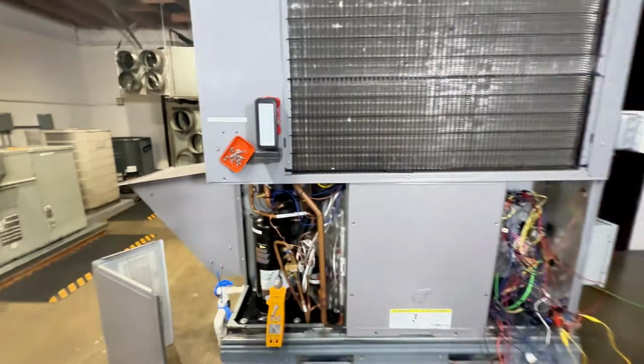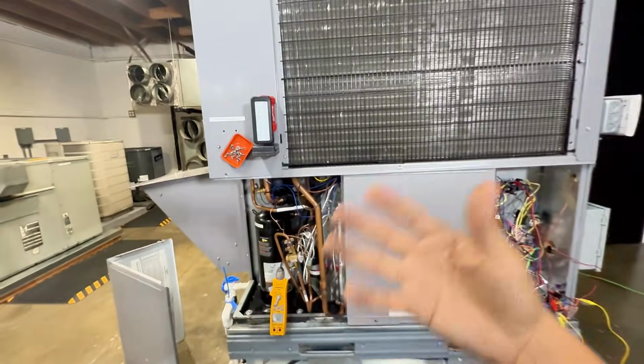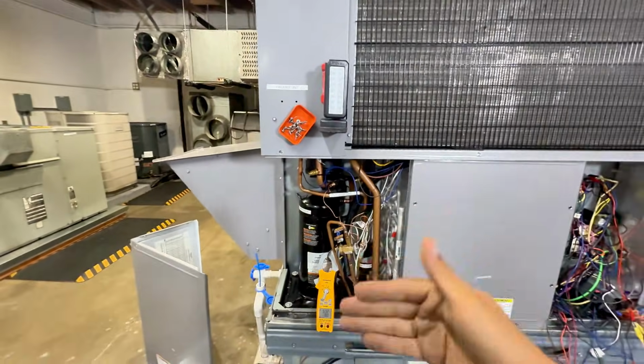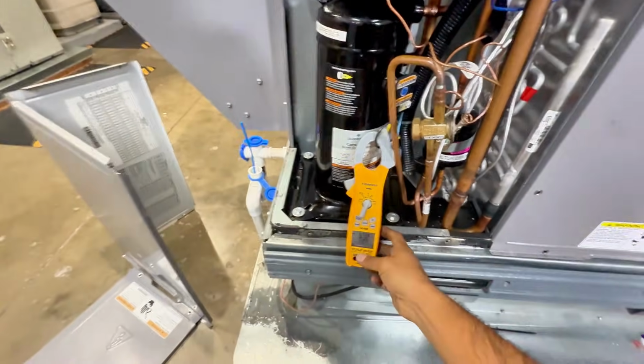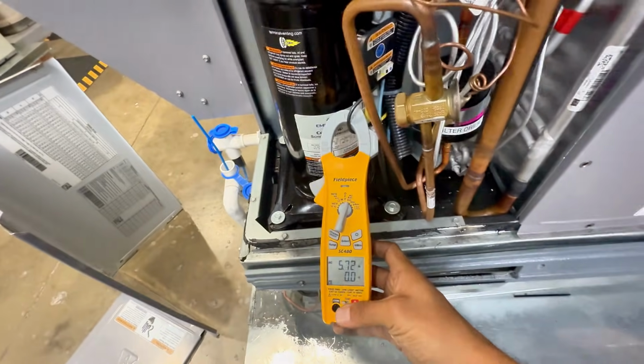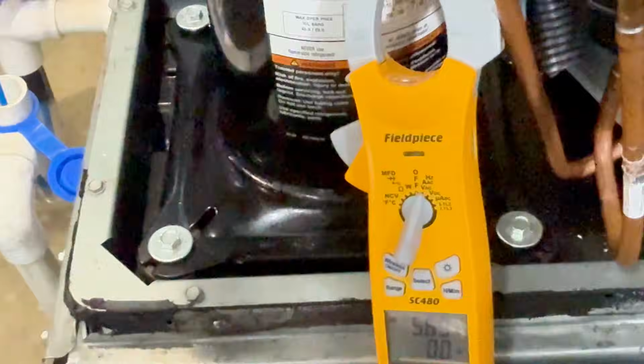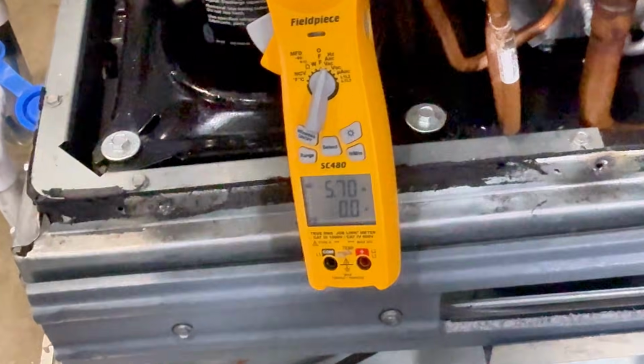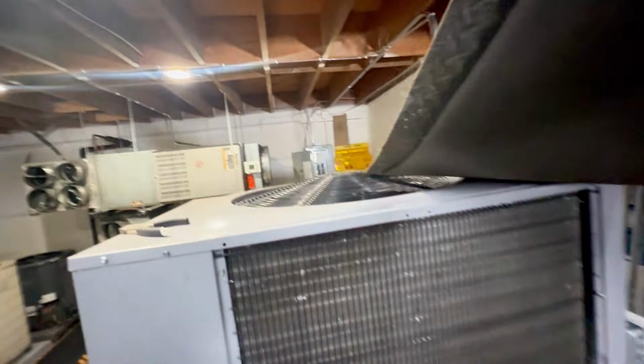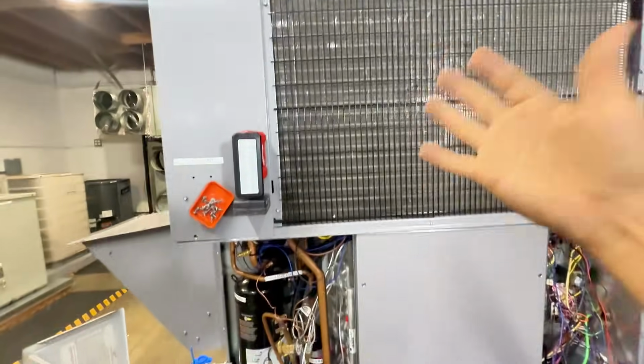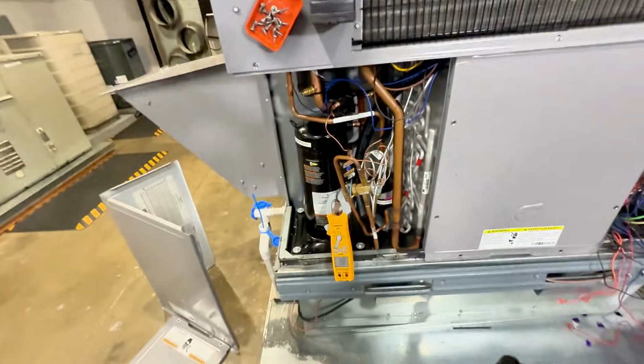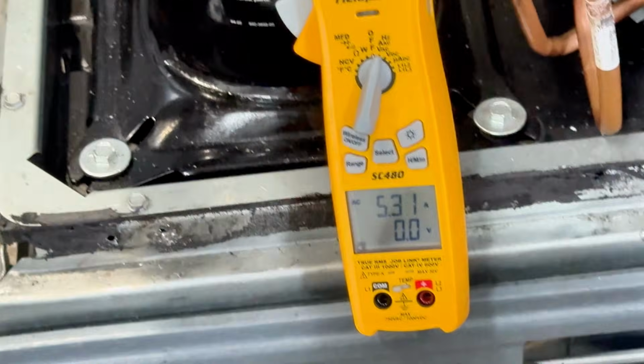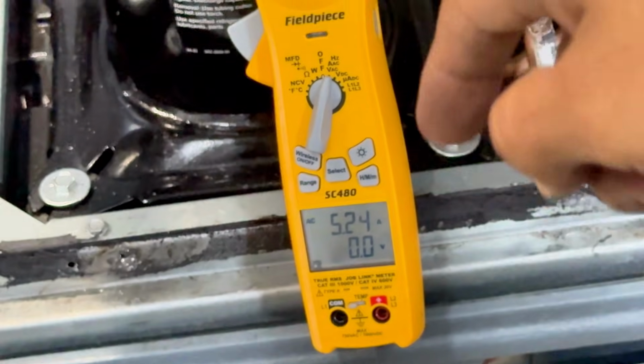When the system is properly charged and all the airflow is good, and you're calling for cooling when it's kind of hot, it's going to be pulling close to that 14. But right now, because I have a dirty condenser, it's pulling 5.7. Look, once I get rid of this obstruction, it can breathe and do its job. It's not going to have a high head pressure. Look at that climb down. You see, it's climbing down.